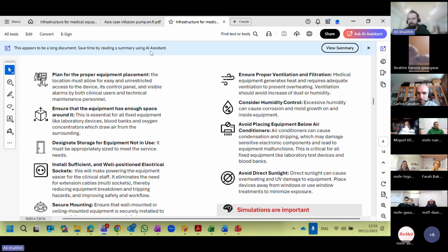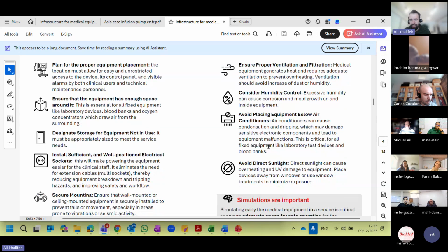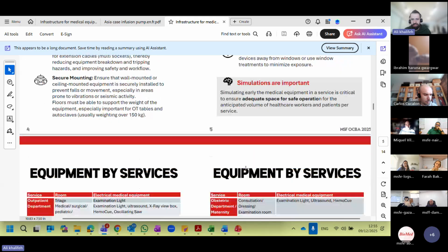Proper ventilation: some equipment needs proper ventilation. Consider humidity control. Also, some equipment needs humidity control, like the lab equipment. Equipment should not be placed below air conditioning, because if we have air leakage or windows opening, the air conditioning could have water leakage and the equipment could be damaged. Avoid direct sunlight. This also causes overheating and UV damage to the equipment.